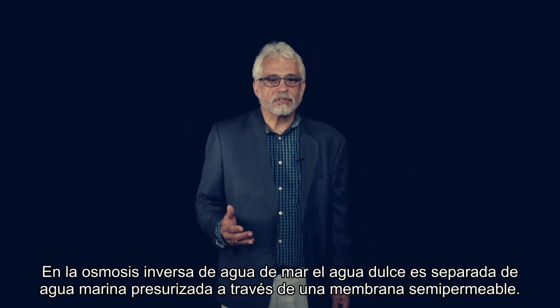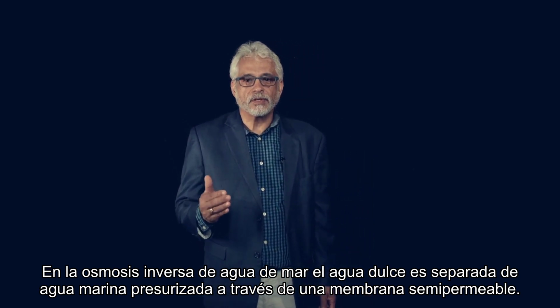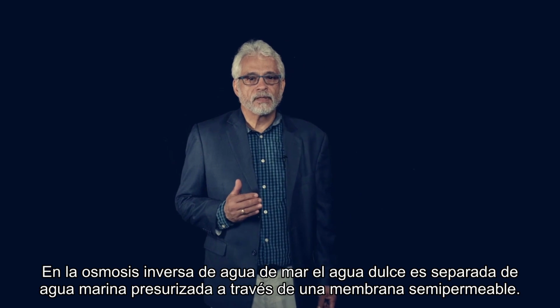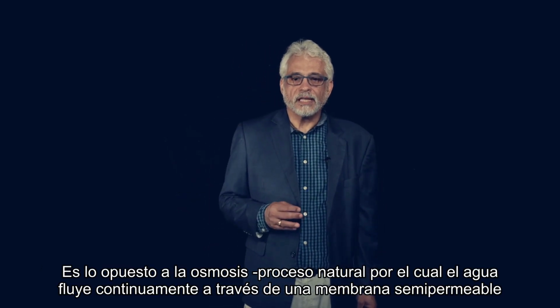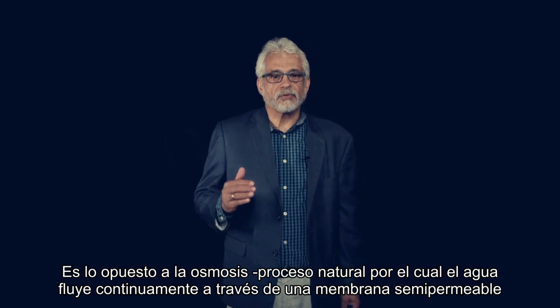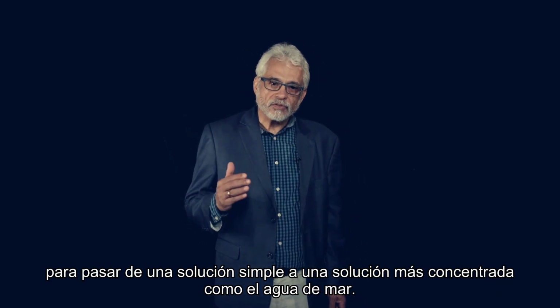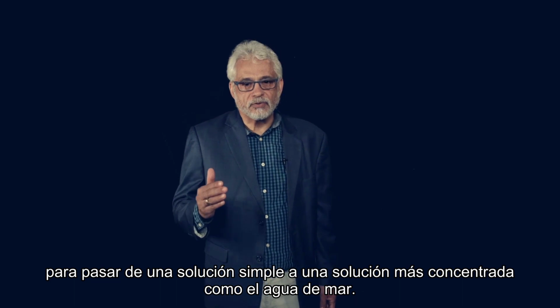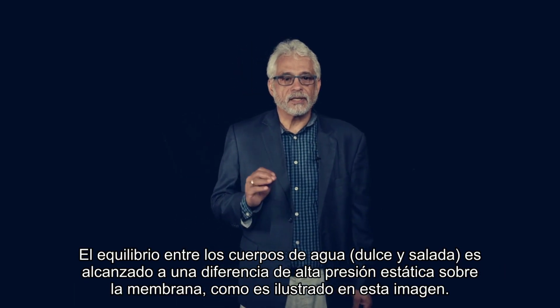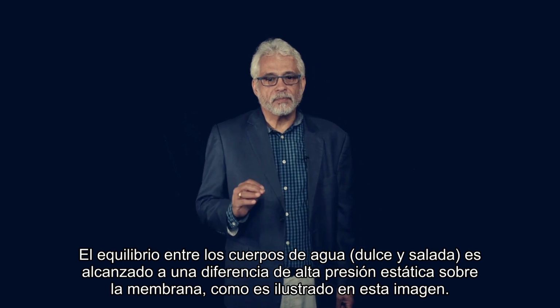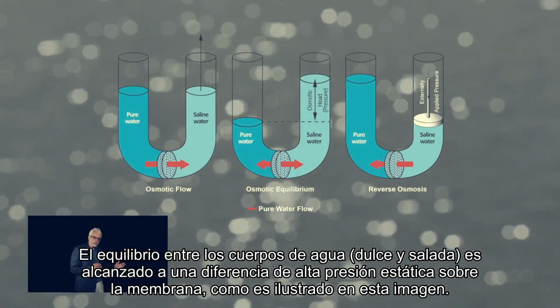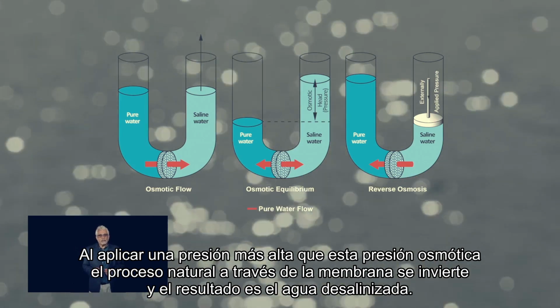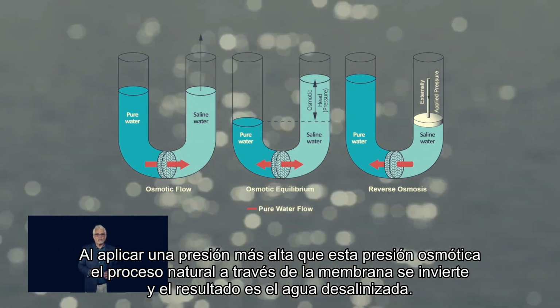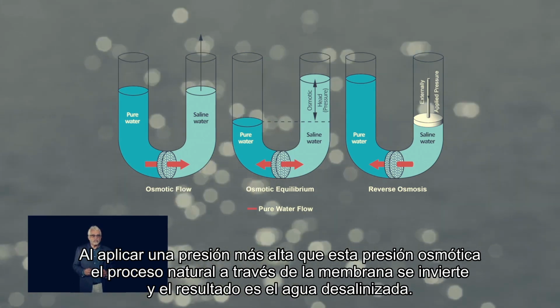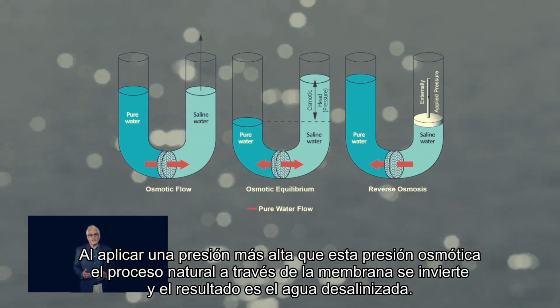In seawater reverse osmosis, fresh water is separated from pressurized seawater through a semi-permeable membrane. This is the opposite of osmosis, a natural process where water flows spontaneously through a semi-permeable membrane from a dilute solution to a more concentrated solution as seawater, until equilibrium is reached at a hydrostatic pressure difference over the membrane, as illustrated in this picture. Now, by applying a pressure higher than this osmotic pressure, a net fresh water flow takes place in the reverse direction through the membrane, so desalinating the seawater.